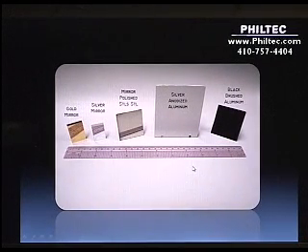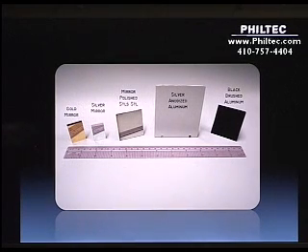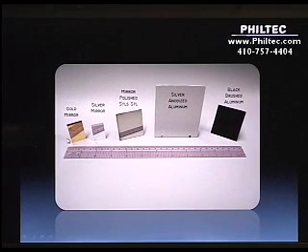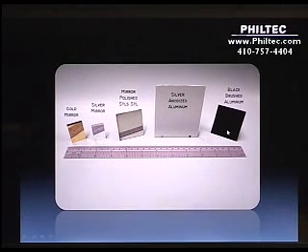When we look at a variety of target surfaces with our probes — and I'll show the results for D models as well as the RC models — we have some interesting results. Here we have five target specimens: a gold mirror, a silver mirror, a mirror-polished stainless steel block, an anodized aluminum which is a dull or diffuse reflector, and a black or brushed aluminum which is also a dull reflective target.